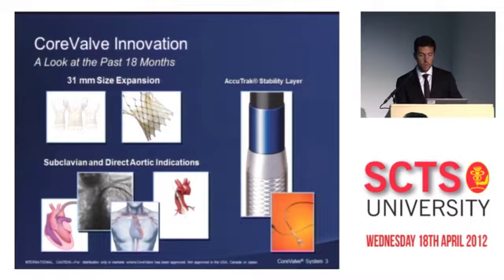If I look back very quickly at the last 18 months, we've expanded the sizes with the 31 millimeter. We have also been granted approval for the direct aortic and subclavian access. CoreValve is the only valve approved for those two indications so far. And we've also launched the AccuTrak stability system, a delivery system that has proven to reduce one of the issues we had, which is higher pacemaker rates. And we've seen since the launch of this product that those centers that have adopted this technology have seen their pacemaker rates reducing.